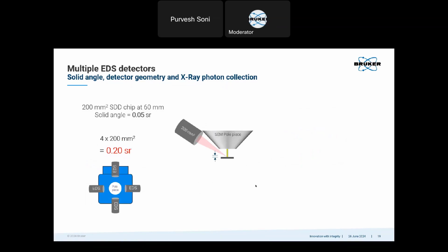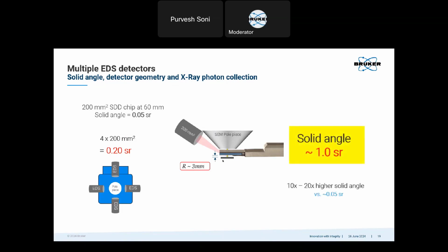So what to do? Let's say we have a detector which is inserted right under the pole piece, very close to the sample. Then we have a very large solid angle of around 1 steradian, just because the sample and the detector are so close. With a single detector, we gain 10 to 20 times higher solid angle compared to a very large area detector, or even 4 large area detectors.